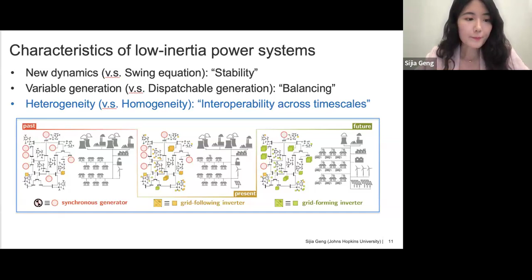Although many of the audience may already be familiar with grid-forming and grid-following inverters, I want to quickly provide some primer on IBR dynamics for those who don't. At one end of the spectrum for IBR control, we have the grid-following controller, which is the most widely adopted technology in the current grid. The concept of grid following is that there is a steady AC voltage waveform that can be measured, and one wants to inject certain power into the grid by forming a current source. The name grid following means they follow or synchronize with the grid voltage waveform.